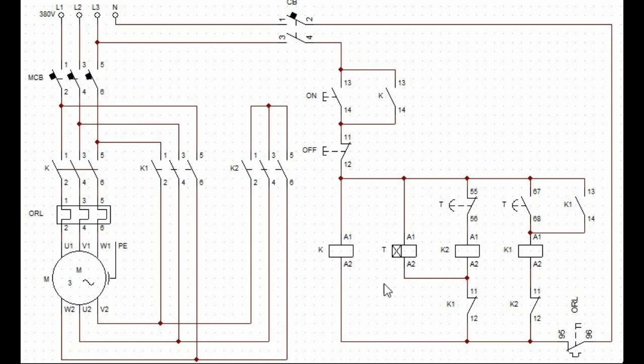After the on switch is pressed, contact 13 and 14 will close and complete the circuit, so voltage is supplied to the off switch normally closed contact 11 and 12, and continues to the magnetic coil of contactor K at A1 and the timer coil A1.